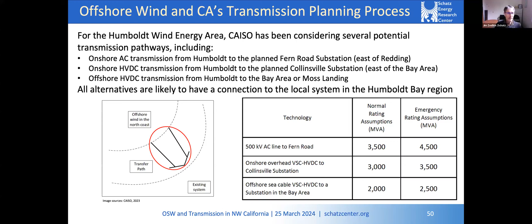This also shows the capacities for a typical high voltage DC line, whether overhead onshore or undersea/underground, at 2,000 megawatts. As Arnie noted, when transmission planning work is done, it's not sufficient to put in a line that handles the new generation capacity by itself—you need to account for contingencies and build redundancy into the system, so if one line is lost, you don't lose all of that generation. Next slide, please.